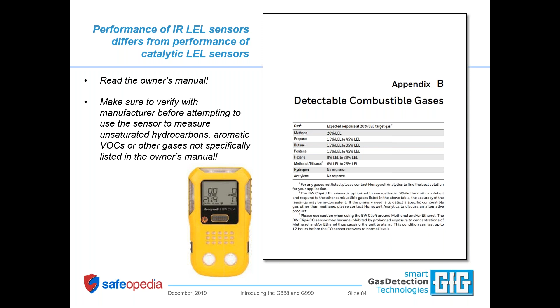And the big difference with our sensors is that they're not cheap. They're truly excellent sensors. Not only is the sensor itself excellent, but the software that we use to interpret the signal of the sensor is really unique as well. If you're going from one gas response curve to another, the shape of the curve is actually different. So what you have to do is to program the sensor with what we call a lookup table. So it stores curves for all of the gases in the library. If you know that you're going to be dealing with something other than methane, then no worries. You pick the propane curve. The propane curve and the methane curve are shaped entirely different.